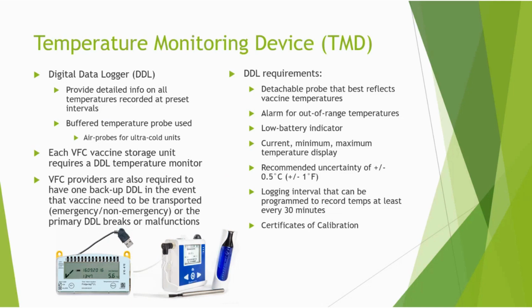DDLs do have certain requirements in order to be acceptable for use by the VFC program, and it should have a detachable probe that best reflects vaccine temps, so that's going to be the buffered probe. It should have an alarm for any out of range temperatures. It should have a low battery indicator. It should have a visual display that displays current min and max temperatures. It should have the recommended uncertainty of plus or minus 0.5 degrees Celsius or plus or minus 1 degree Fahrenheit. It should also have a logging interval that can be programmed to record temperatures at least every 30 minutes, and it must also have an active certificate of calibration. Expired certificates of calibration are not accepted by the VFC program. Next slide, please.